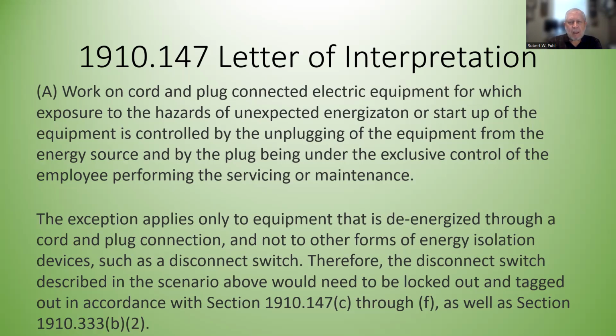1910.147. And you can kind of see why, because they put this exception in there for a simple piece of equipment. And they thought, well, do we really need to have elaborate protection for a simple piece of equipment? And probably not. So they said, all right, you unplug it, you keep that plug in the exclusive control of the person doing it. So now what happens is people do this, and you'll see it a lot. They take a portion of a standard, exclusive control, and they apply this across the board to everything. And that's not the way it goes. You can only apply that exclusive control to this.